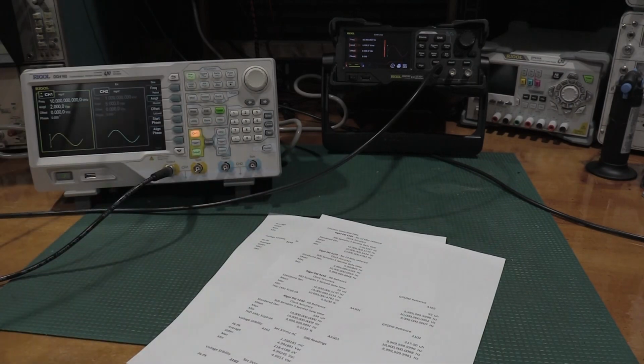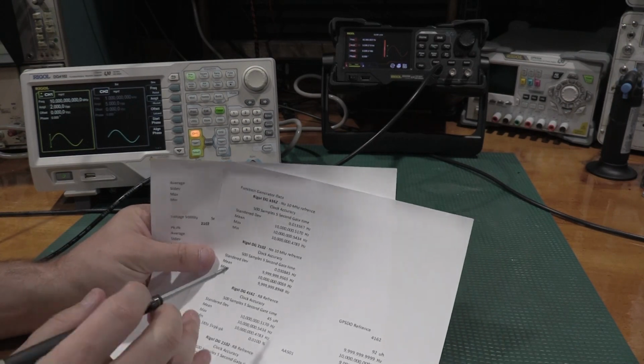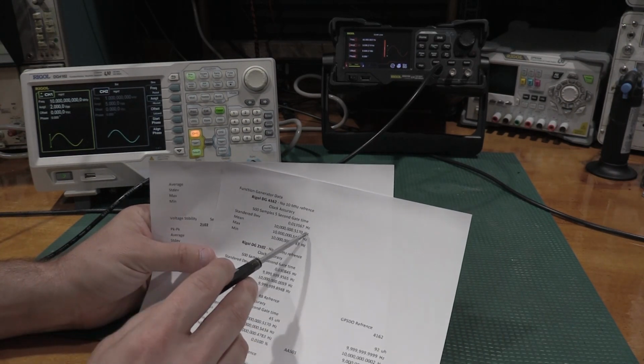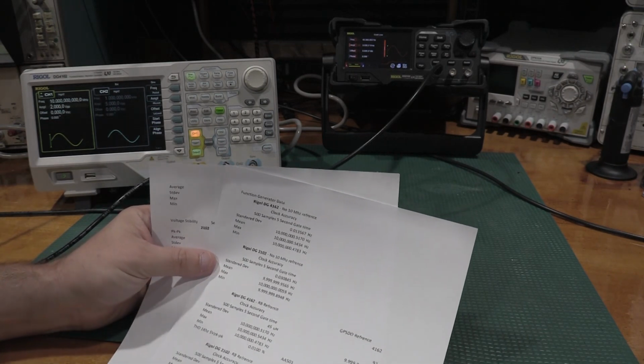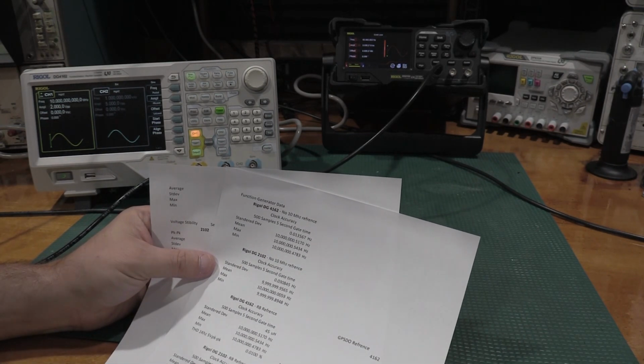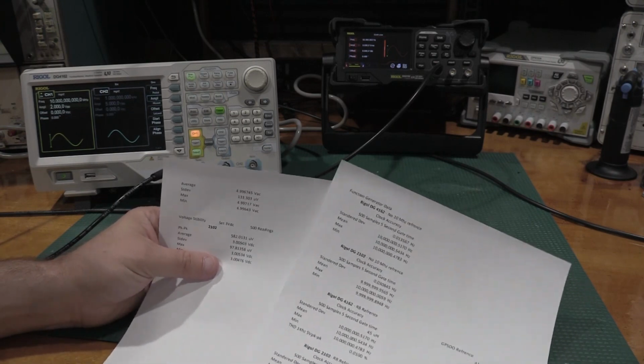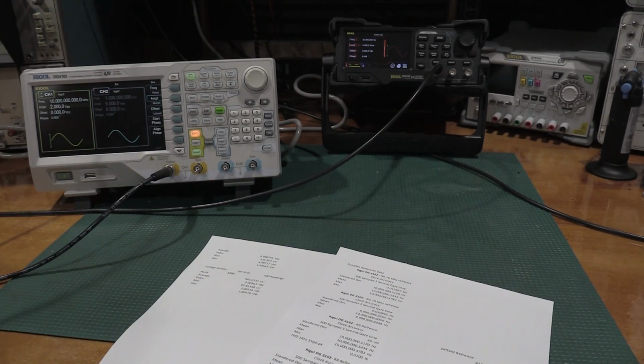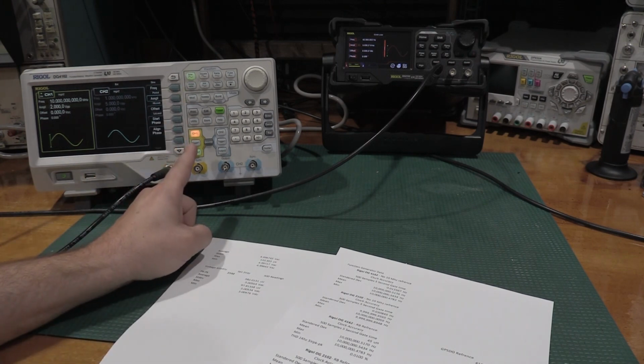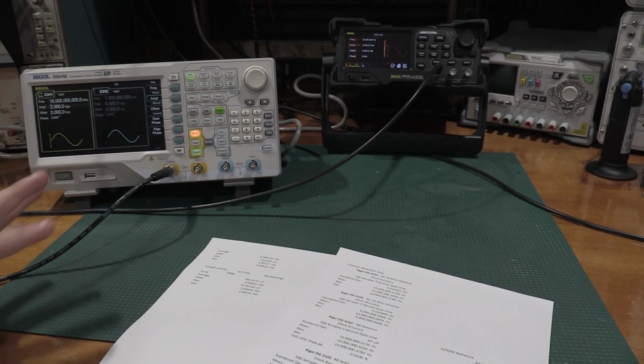The important specification that I'm most concerned with, especially if you're doing a scope cal or something like that, would be the standard deviation on the clock. That's where these units are really going to differentiate themselves and shine. A couple of other tests I did were voltage stability over time, where I set up the 6500 to take 500 readings at 10 averages on AC and DC. Found out this guy can't do DC, but that guy can. So that is one difference between the two.